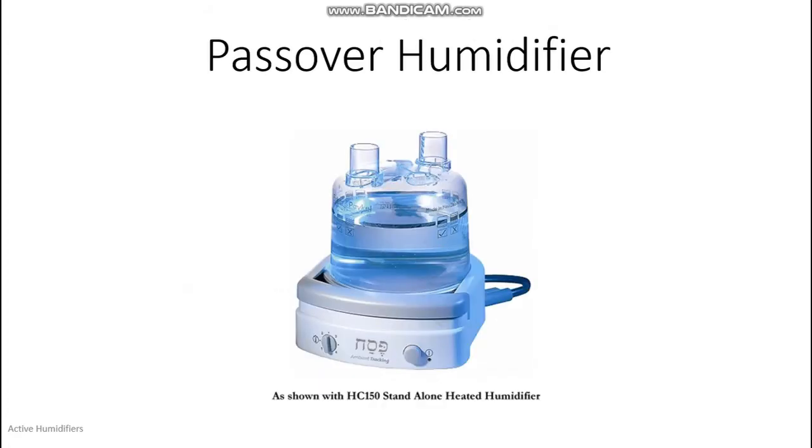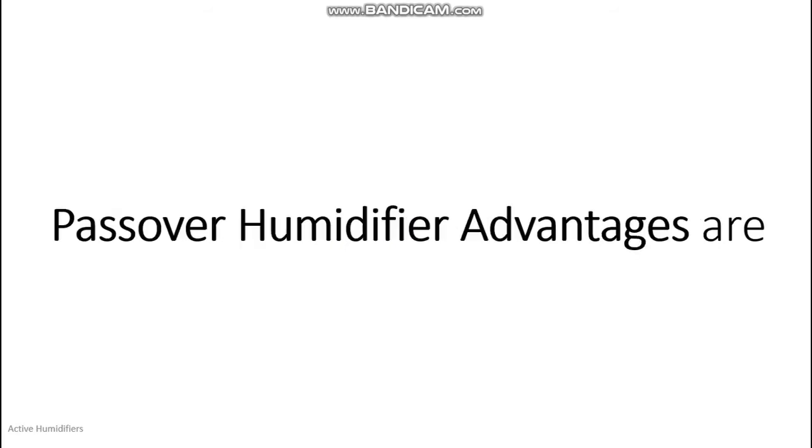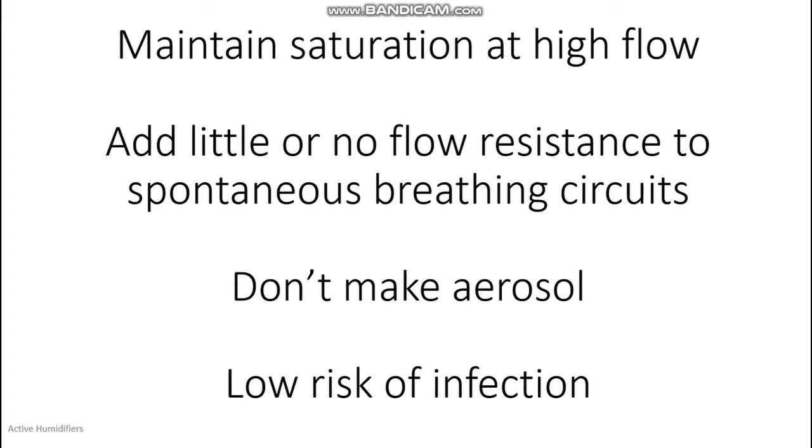Pass-over humidifiers direct gas over the water surface. Pass-over humidifier advantages are: they maintain saturation at high flows. They add little or no flow resistance to spontaneous breathing circuits. They don't make aerosol. And they have a low risk of infection.